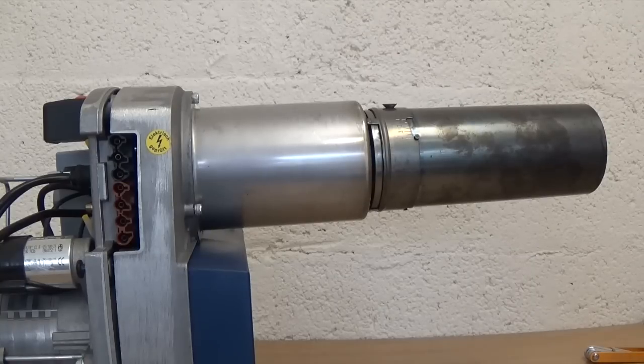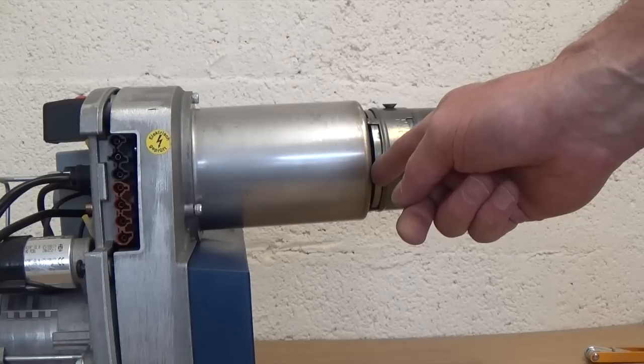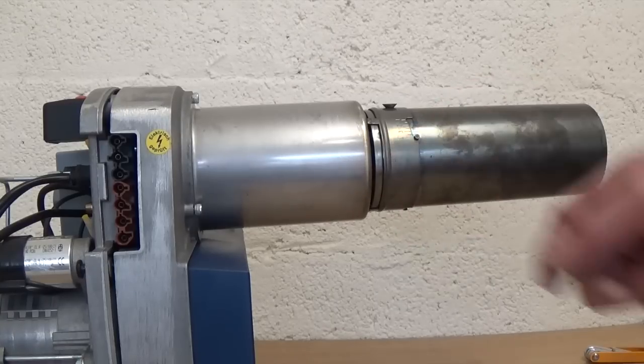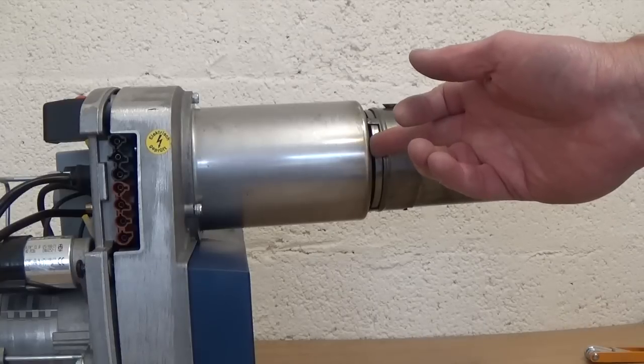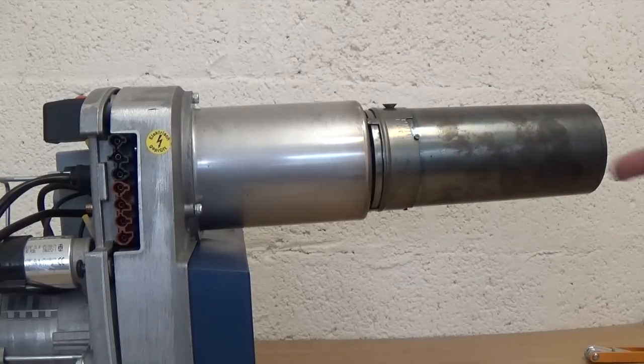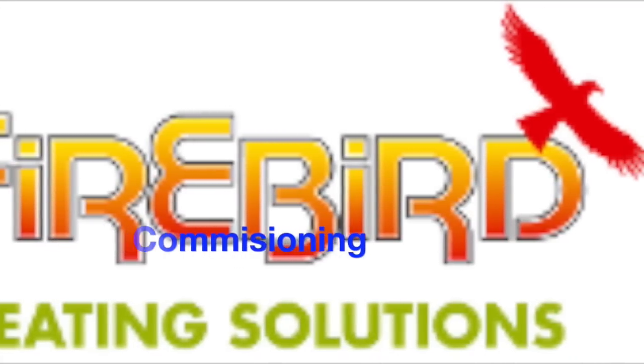Hot combustion gases that leave the combustion tube are then recirculated back to the suction side through a gap in the blast tube chamber. By doing this, the NOx gases are reburnt, which in turn reduces the NOx levels. Also, the extra oxygen that is leaving the blast tube to be recirculated back through the gap is being used to produce a blue flame.